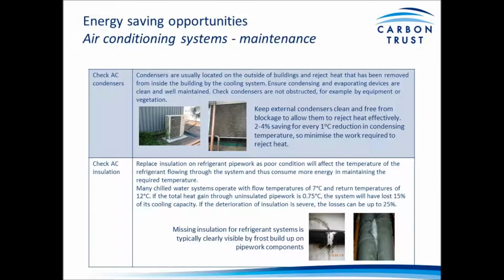Maintenance of AC systems is again essential for efficient operation. Internal evaporators and external condensers are effectively transferring thermal energy from inside to outside when in cooling mode. So if they have to work harder to blow air over the coils to gather or reject heat due to blockages on fins or filters, then this requires more energy within the system. And again, roughly 2 to 4% saving per 1 degree C in condensing temperature.